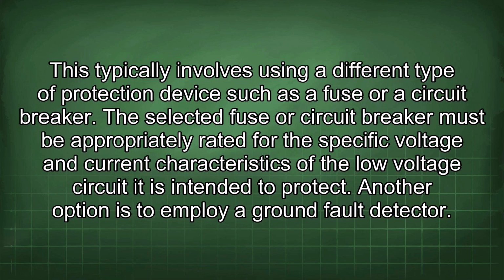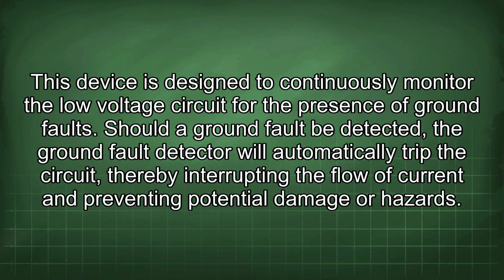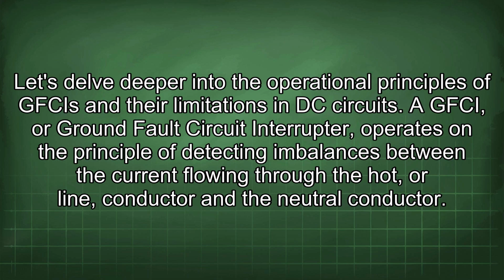Another option is to employ a ground fault detector. This device is designed to continuously monitor the low-voltage circuit for the presence of ground faults. Should a ground fault be detected, the ground fault detector will automatically trip the circuit, thereby interrupting the flow of current and preventing potential damage or hazards. Let's delve deeper into the operational principles of GFCIs and their limitations in DC circuits.